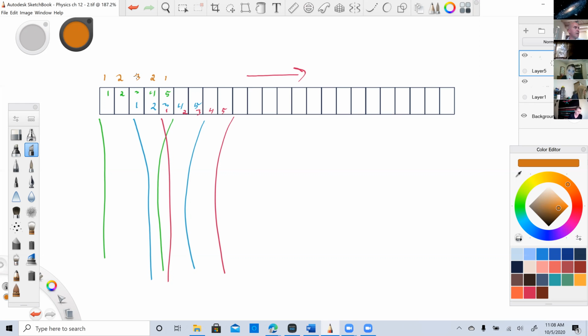Now, number of crystals and shape: 120 to 250 rectangular shaped piezoelectric elements. So basically this is what I've drawn. I didn't draw nearly 120, but you get the idea. Each crystal is about a wavelength in width, so the width is about equal to lambda. They could be up to 10 centimeters long.